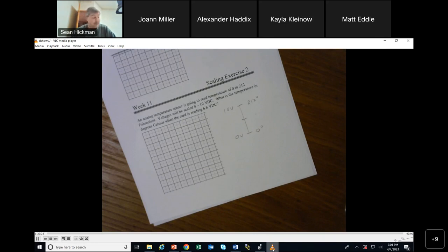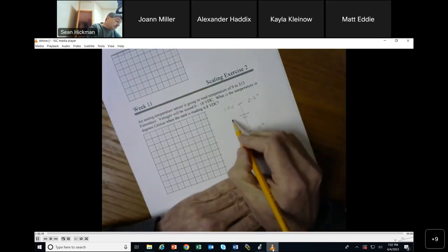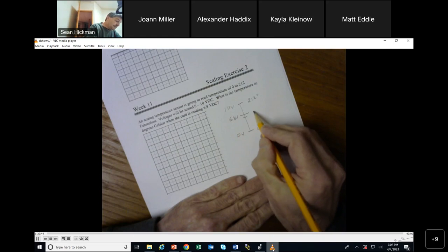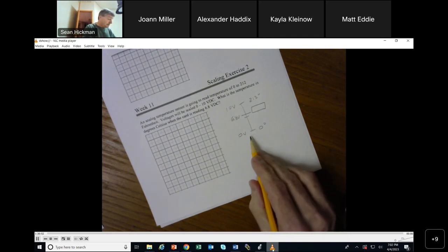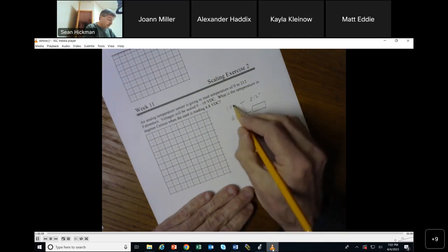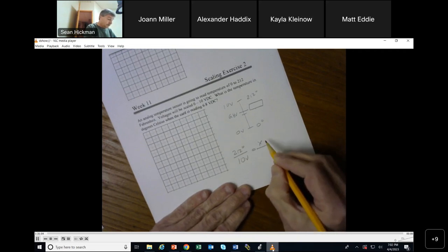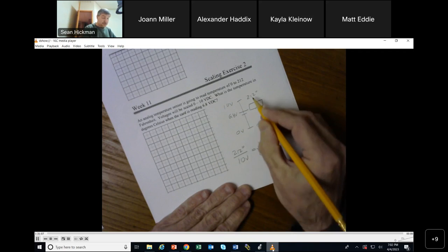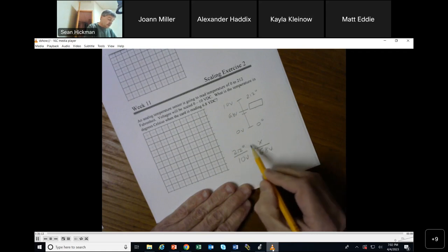106, you just cut it in half. Yeah, it's easy, right? What if I get 6.8 volts? What's my temperature at 6.8 volts? Well, it's all scaled. Because both of these start at zero, it's just 212 degrees is to 10 volts as X degrees is to 6.8 volts. It's just ratioed like that. You got 144.16. Yeah, you're cross multiplying like this.